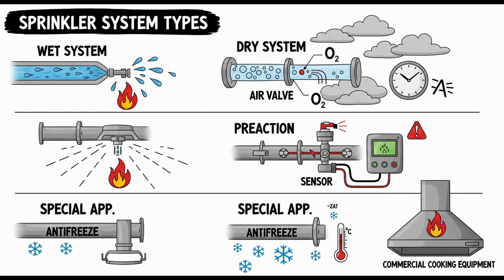Crucial detail. Very. Placards are also required. One on the main system riser indicating how many remote antifreeze systems are supplied by that riser and where they are located. So you know where these small systems are tapped in. Right. And another placard right on the antifreeze system's main control valve. This one needs to state the manufacturer, the type and brand of the antifreeze solution used, its minimum rated use temperature, and the total volume of the solution in that specific system. Important information for anyone maintaining the system: what's in it, how cold it's rated for, and how much they need if they have to refill it.